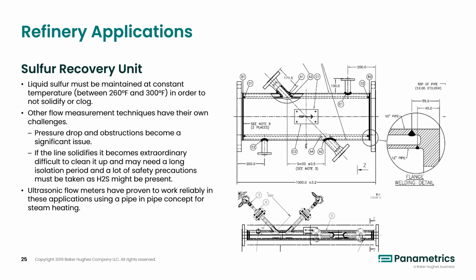In the sulfur recovery unit, liquid sulfur must be maintained at a constant temperature between 260 degrees Fahrenheit and 300 in order to not solidify or clog. Other flow measurement techniques have their own challenges with pressure drop and flow obstructions. If the line solidifies, it becomes extraordinarily difficult to clean up and may need a long isolation period, and a lot of safety precautions must be taken due to the presence of hydrogen sulfide. Ultrasonics have proven to work reliably in these applications using a pipe-in-pipe concept with steam heating. The picture on the right shows two examples of such systems with proven reliability for uptime, which is a common theme from a Panametrics ultrasonic flow meter.